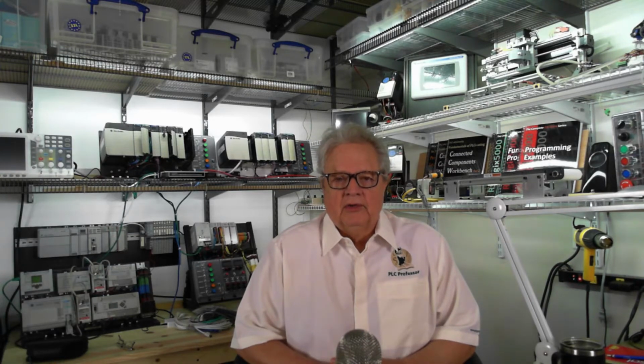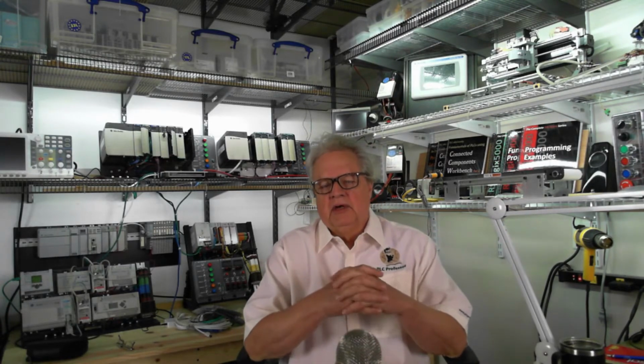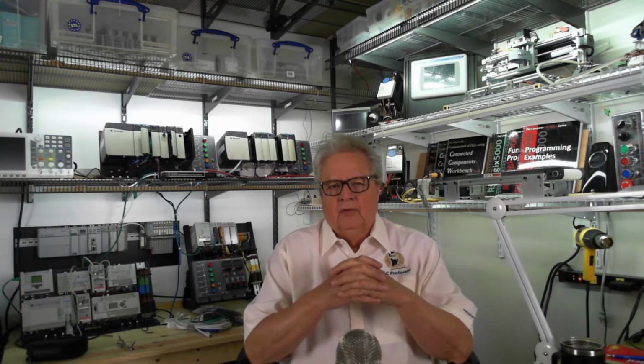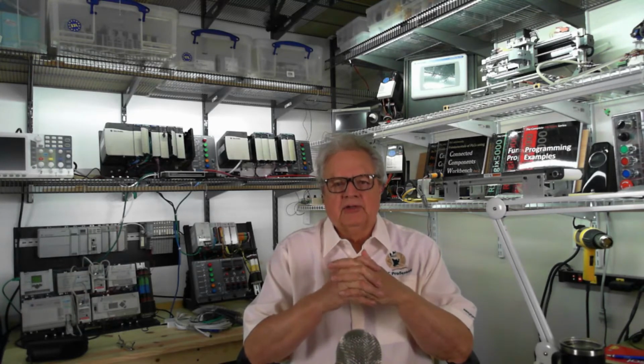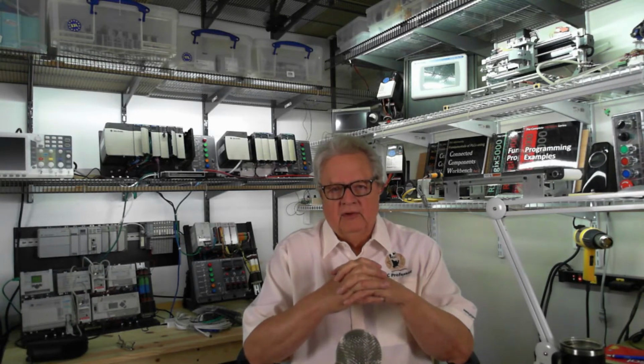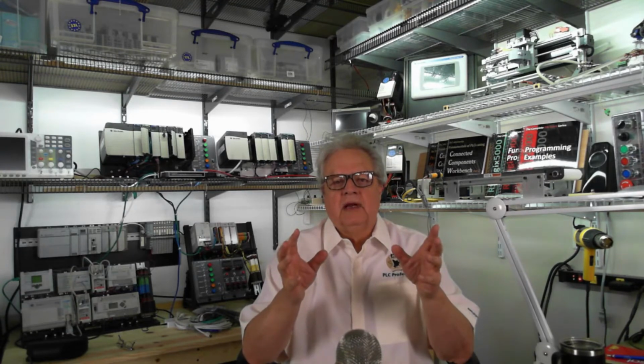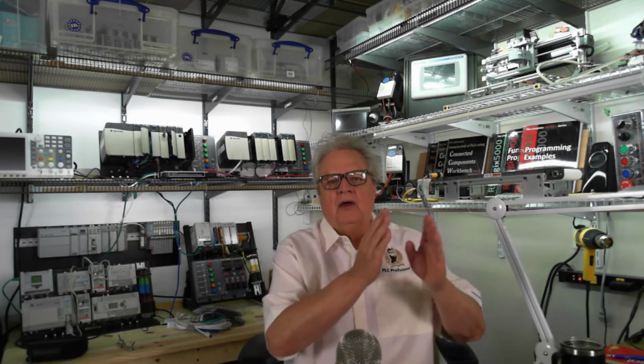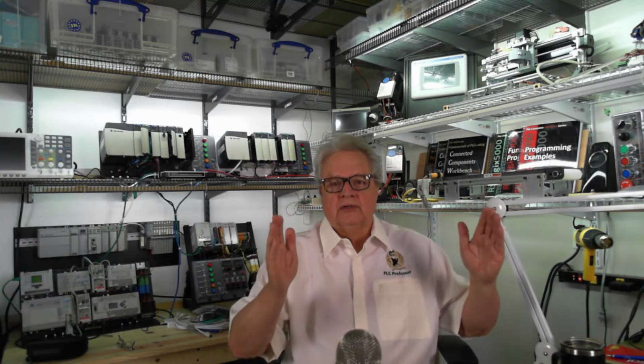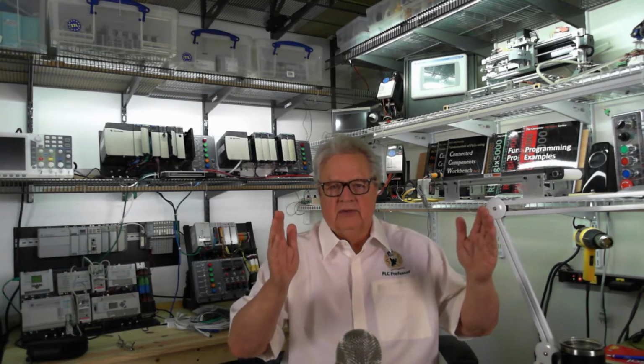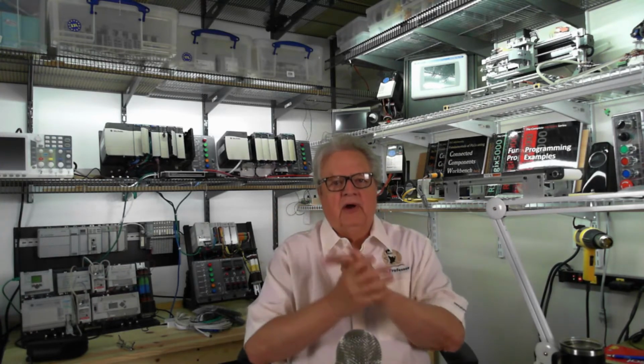So right now what we're going to do is consider what is a simulator. Now, there's a difference between an emulator and a simulator. With the MicroLogix 1000, 1100, or with MicroStarter Lite or MicroStarter, there is an emulator, RSEmulate 500. It emulates the processor. That's all it does. It does not simulate a controller. Remember, a controller is a processor and the I/O interfaces together. An emulator only emulates the processor.